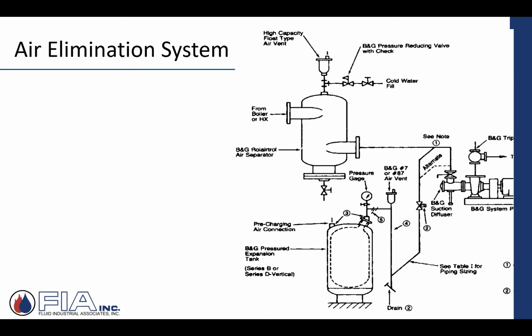They call it air elimination as a simple statement. Any air that gets released from that water that gets heated, get rid of it. I don't need it. I don't need to control it. I want to get rid of it. I want to eliminate it. Because down here is, in this case, a bladder style expansion tank or compression tank that has a charge of air in the shell. In this case, it's in the shell of this bladder tank.